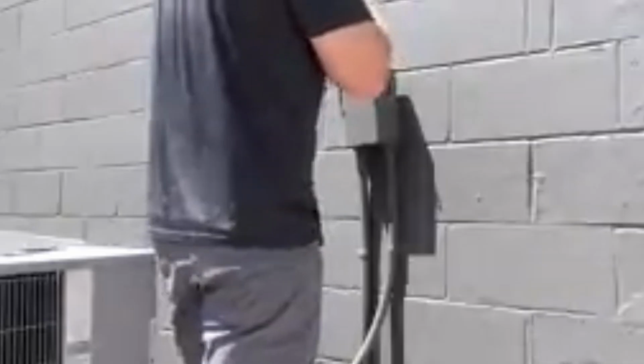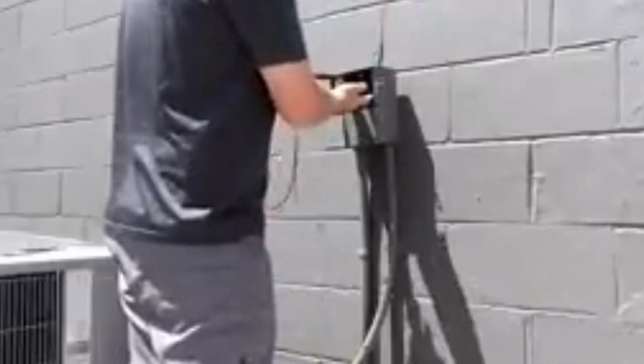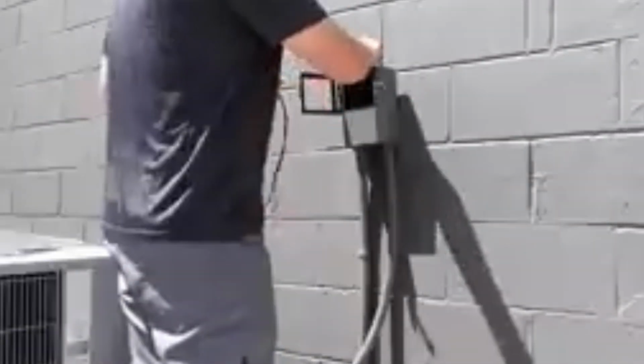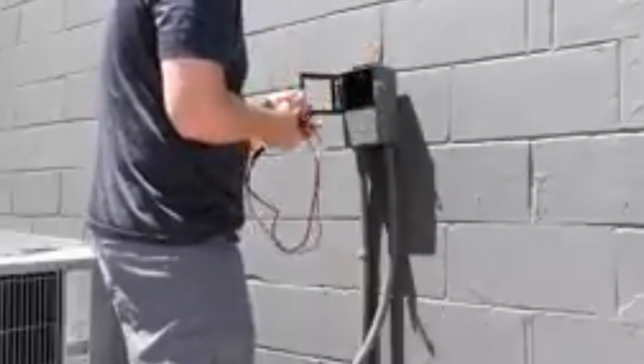First thing, whenever we're going to work on any electrical, make sure you wear your safety glasses, shut off the disconnect, and then test to make sure that each leg has no voltage to ground. First, our display should show next to no voltage at all.